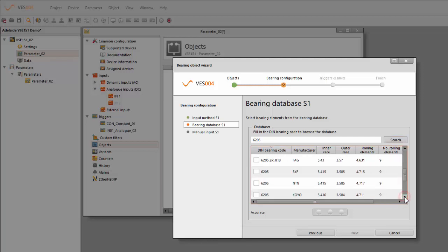Once you do that, you'll see all the different brands of bearings in there, and you'll find that it's very, very important to know, if possible, which bearing manufacturer made that bearing. This one here is not actually too bad because there's only a few different bearings in there, but if I put in the wrong one, I'll show you what will happen. So my correct bearing is this one here, down here, 6205 SKF. So if I click it, you'll see this little green dot coming there.